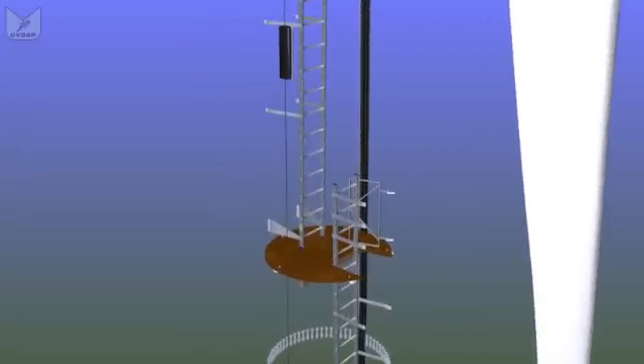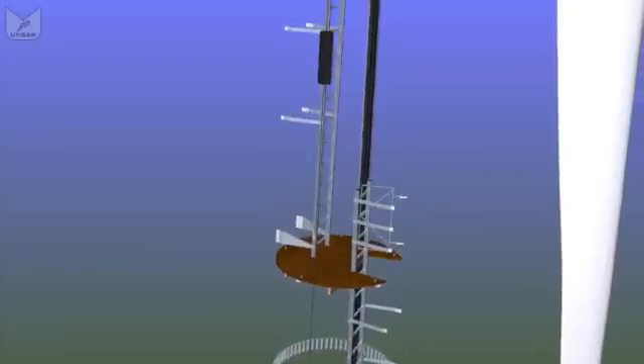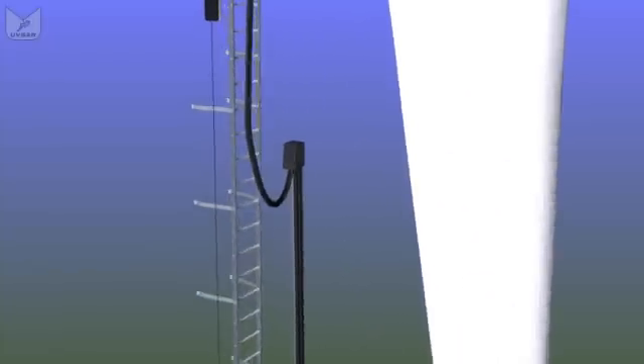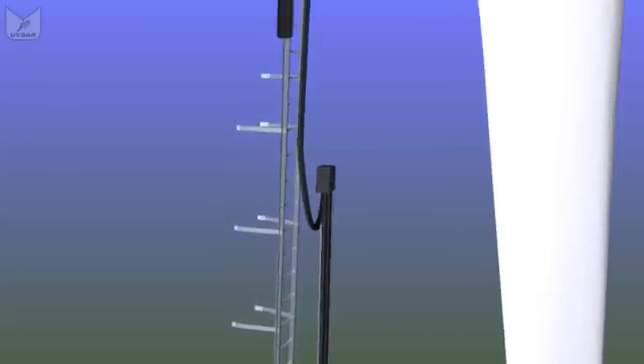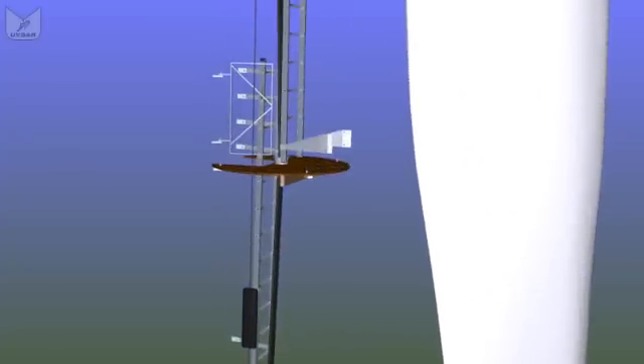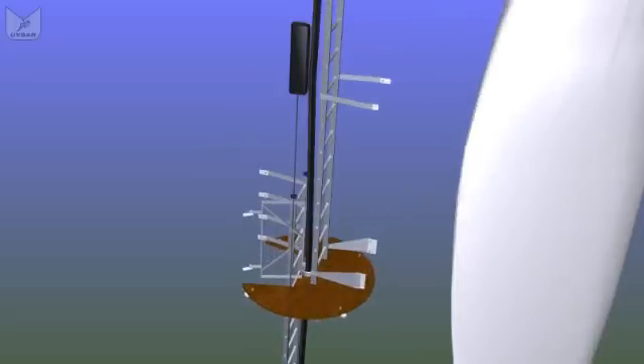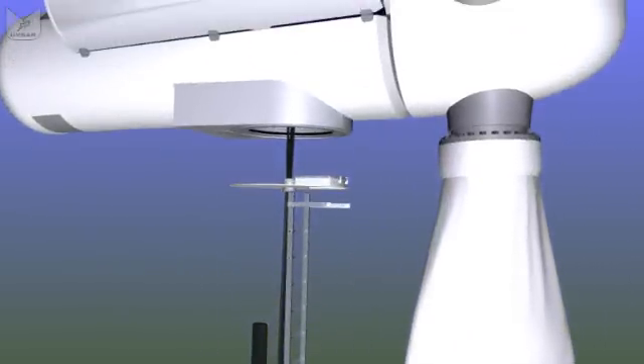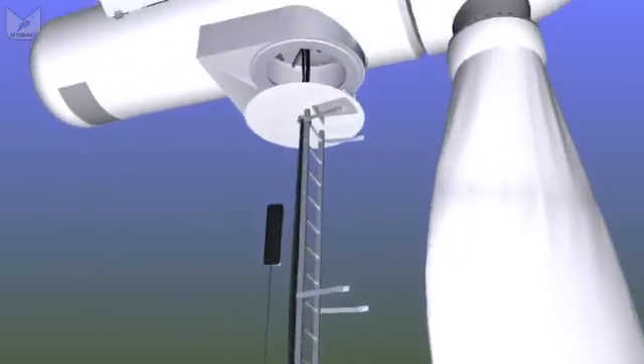But eventually, the main cables stop being attached to the wall, and they hang freely in the center of the tower, so they can twist as the nacelle rotates to face the wind. If they twist too many times, the nacelle will spin itself around to remove the twists. But as we move up, now the cable goes through a hole in the center of each platform, and at the top of the tower, we have a steel platform with a sealed trapdoor, which we call the yaw platform.